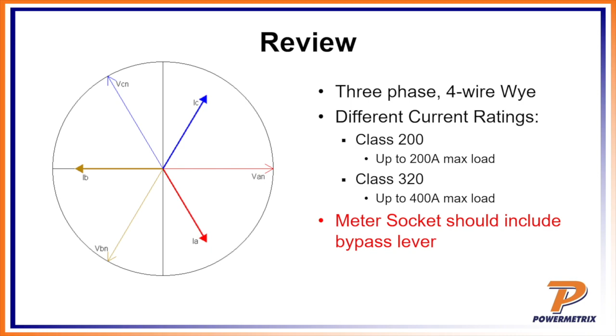With something Ray and I highly recommend, if you have a class 320, and especially if you have a 277/480 volt, make sure you've got a bypass switch on that meter. What happens if I don't have a bypass switch? It's going to be very dangerous. I would follow all of my utility recommendations when you remove a meter, or if you're doing any type of service on those meter cans. Make sure I follow my safety guidelines, because you've got a lot of current and voltage there possibly. That's a must.